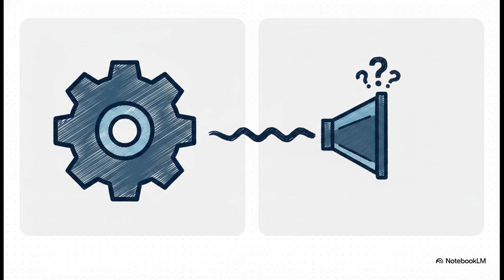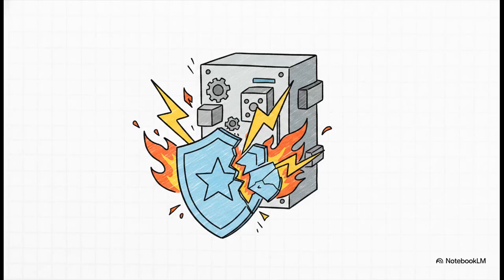Now, think about those numbers for a second. There is a really stark contrast there. We've got a contactor officially rated for 400 amps, but it's deliberately throttled by a fuse rated for only 315 amps. Why on earth would we intentionally bottleneck a 400 amp piece of heavy-duty equipment with a 315 amp fuse? Well, it comes down to precision engineering and some very deliberate trade-offs. The secret here is the protective margin. That lower fuse rating is completely by design, not some typo from the manufacturer.